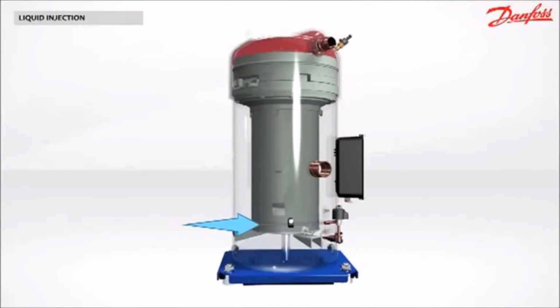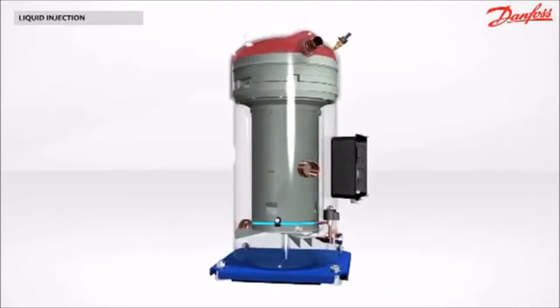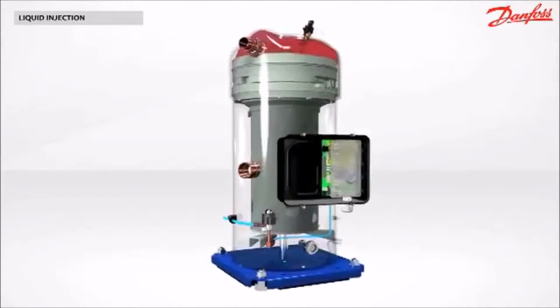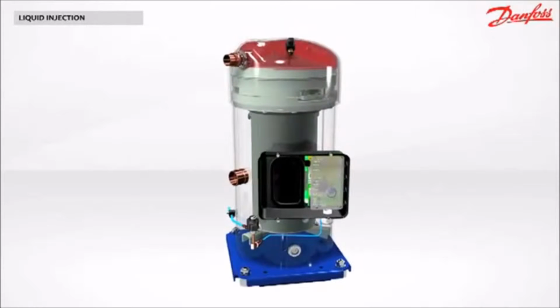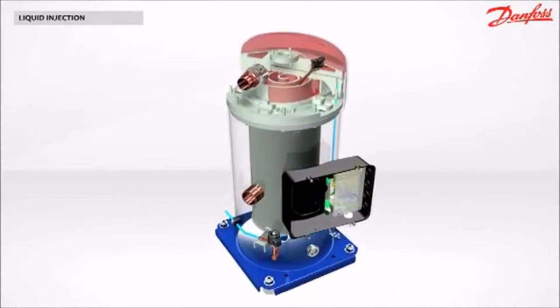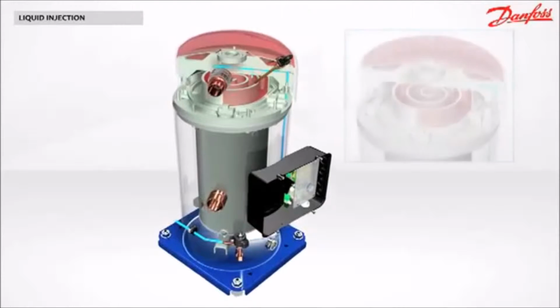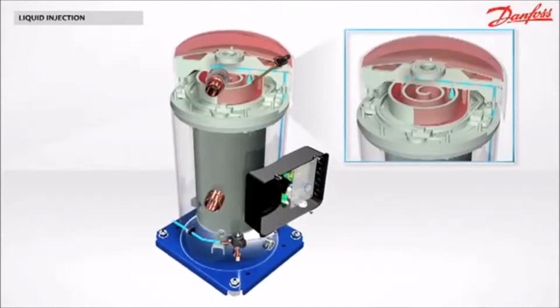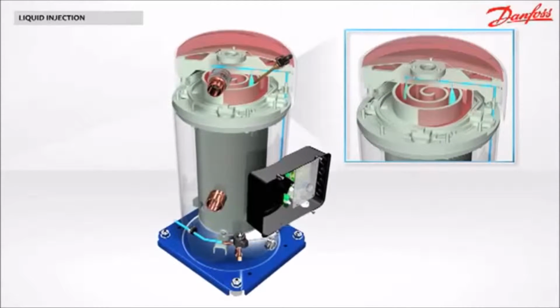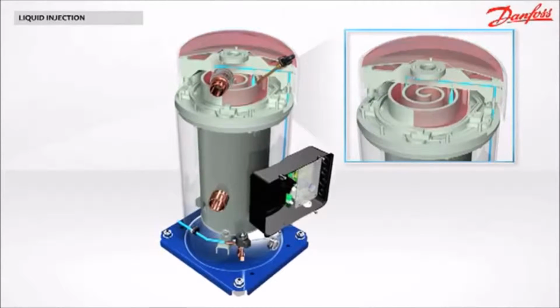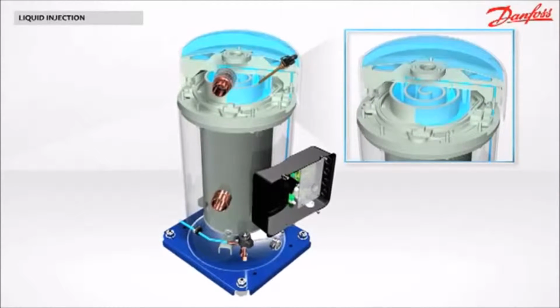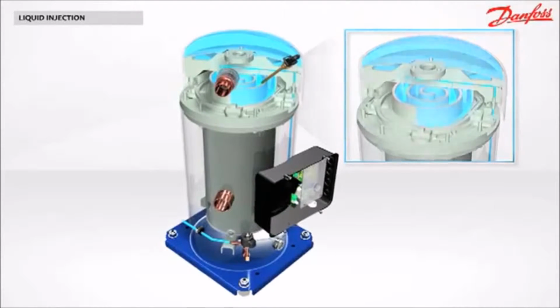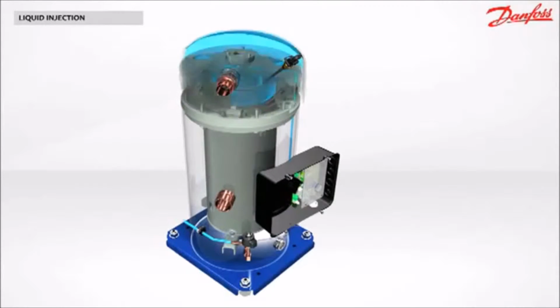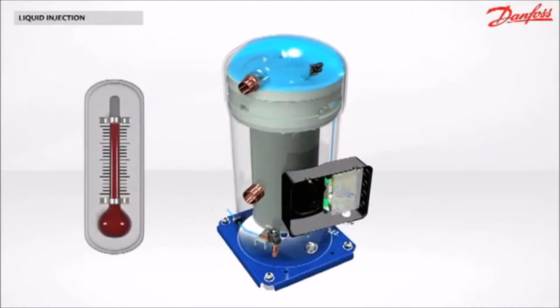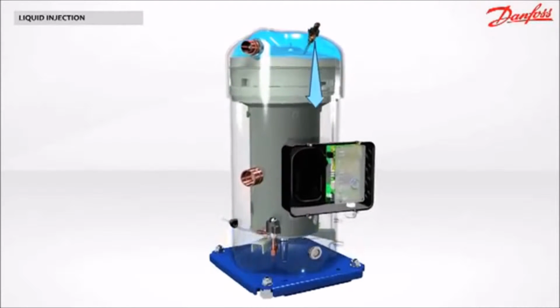The liquid leaving the condenser is re-injected in the scroll set of the compressor through an internal piping. The injection is made in 2 different points of the intermediate compression pockets. The discharge gas is cooled down by the liquid injection. When the temperature is back to normal, the liquid injection is stopped.